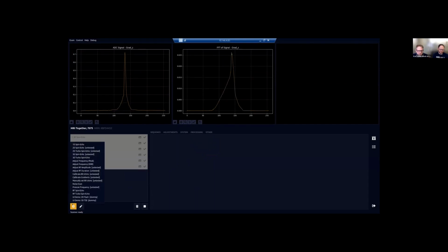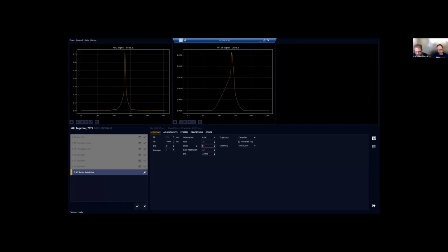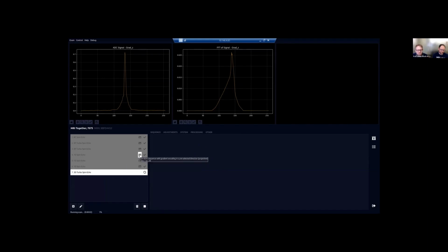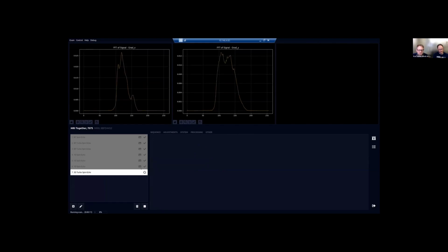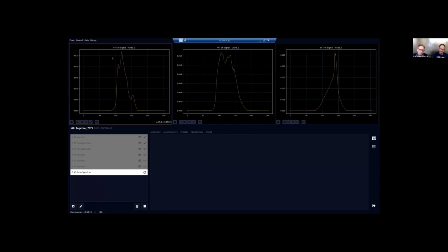Before saying more about that, I just quickly want to start an imaging scan, because the imaging scan will take about 2 minutes. We can already have the scan running in the background, and I'll say more about this later. I'm just going to start the imaging scan. With these scans before, we have now acquired 3 projections in the different directions. Whenever a sequence creates a result, you see this icon here with this image. If you click on that, you can load these results in the different viewers. In this case, I loaded the projections in the X, Y, and Z direction, so kind of basic projection imaging.